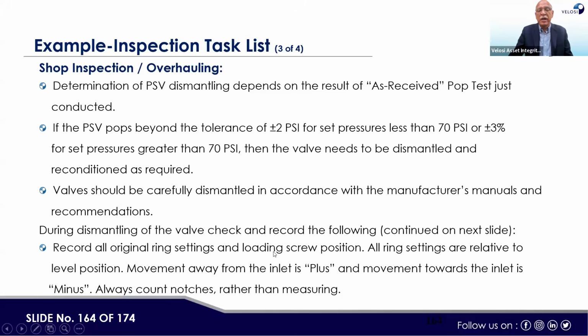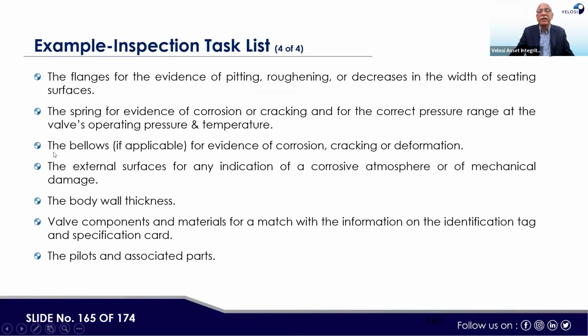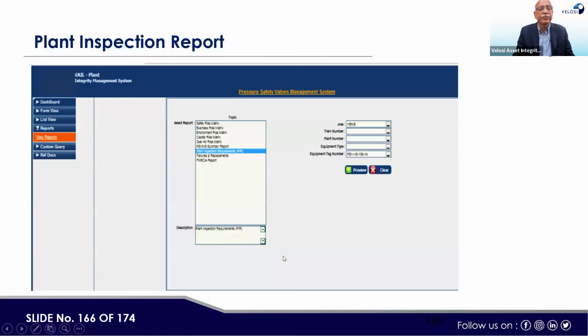Record all original ring settings and loading screw position. All ring settings are relative to the level position. Movement away from the inlet is plus rather than minus. Then the flanges should be checked for evidence of pitting, roughness or decrease in the width of seating surfaces. The spring should be checked for evidence of corrosion cracking. The bellows, if applicable, should be checked for evidence of corrosion cracking. The external surface should be checked for any indication of corrosive atmosphere or mechanical damage. The body wall thickness should be checked. Then valve components and material should be checked for a match with the information on the identification tag and specification card. The pilot and associated parts should be checked. So this is the report we need to follow.